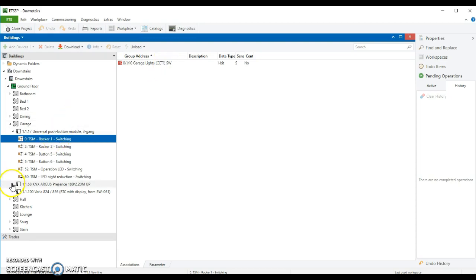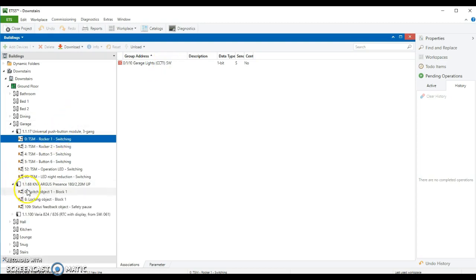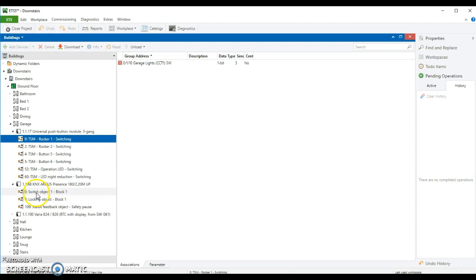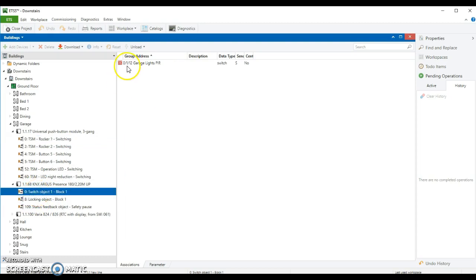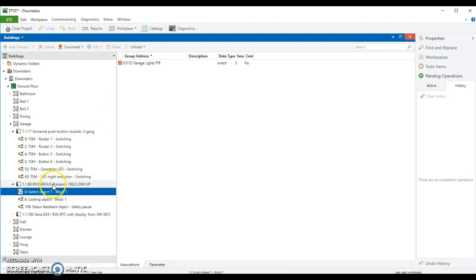I've also got a presence indicator. And in this, there's two channels, or three channels, but two channels that are functioning. There's a switch object. And this is the one that, when presence is noted by this presence monitor, it will send a one to this address. So 0/1/12.